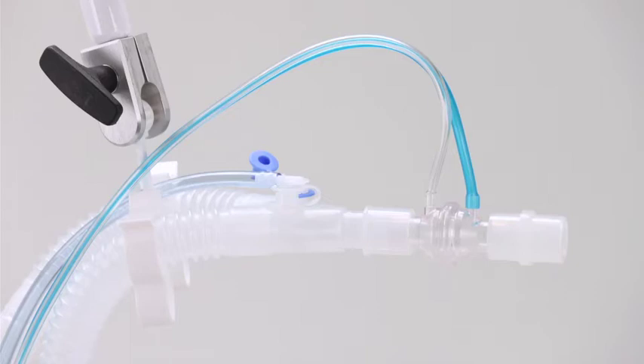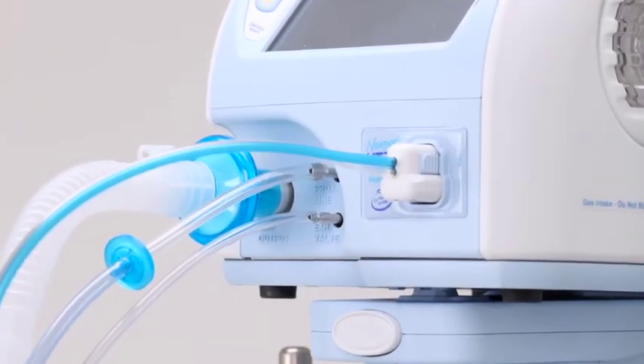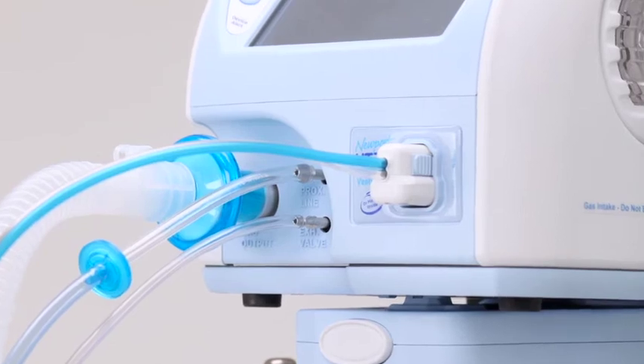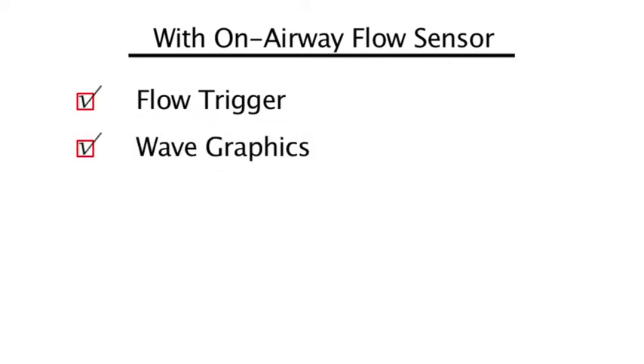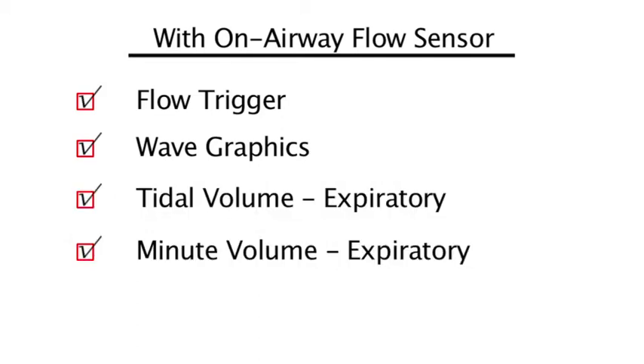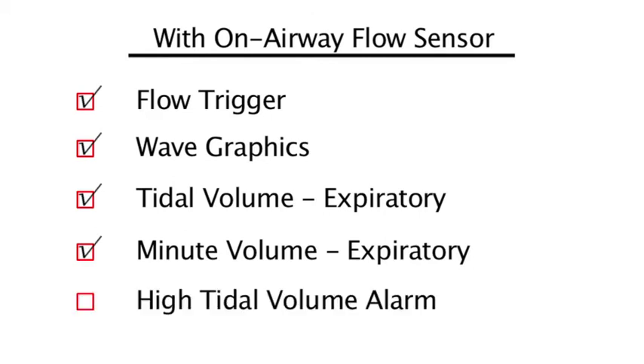Use the 15-22mm adapter supplied with the flow sensor to attach the sensor to the patient interface or heat-moisture exchange filter as needed. When the on-airway flow sensor is plugged into the front panel of the HT70 Plus model, the ventilator will automatically recognize it, enable flow triggering, and display real-time graphics in the wave screen. It will also automatically change the monitored tidal volume and minute volume to exhaled volumes. In addition, you can then set a high tidal volume alarm to alert you if the exhaled volumes become higher than desired.